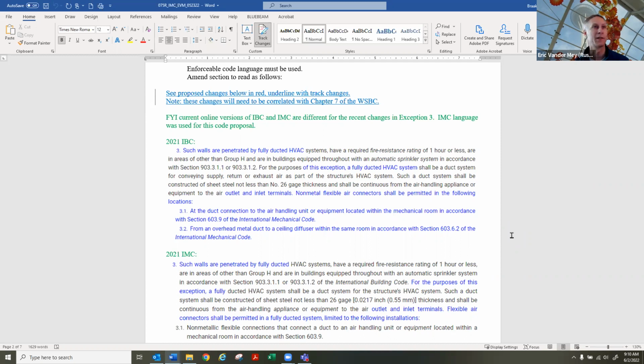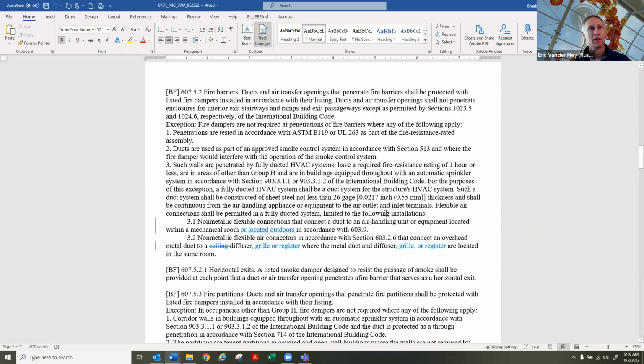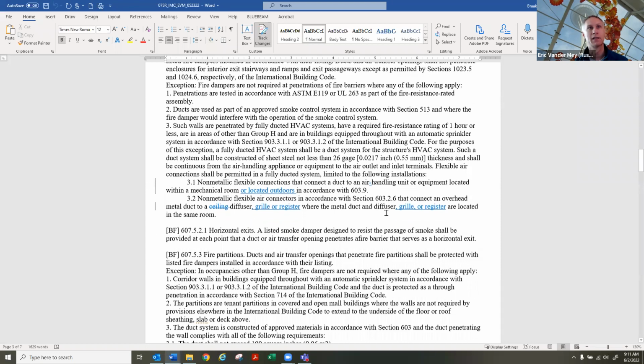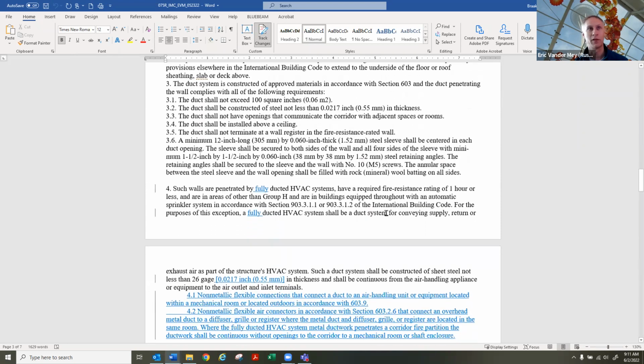So why don't we look at the language I used on the next page, and then we'll go from there. So again, my original proposal was more extensive to this section. So for the fire barrier section, I'm recommending just the changes that are showing in blue, to have a little bit broader language than just say diffuser, to say diffuser, grill, or register, to reflect how it's described in chapter 6 of the mechanical code. And then I also was recommending a clarification that the unit could be located outdoors. So essentially, this now has clearer language for what is the fully ducted system and how that is treated. It does allow for the flex connection at the unit.